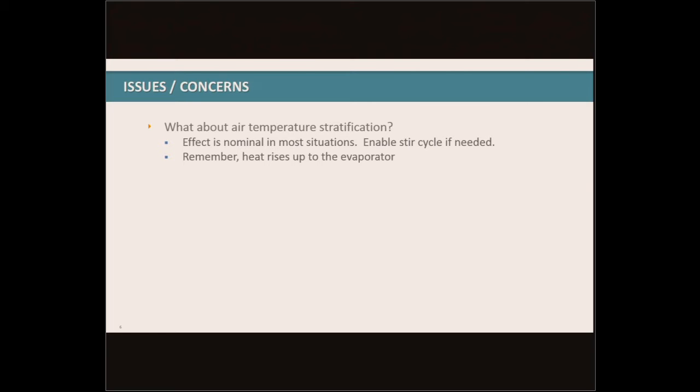The important thing to remember is that heat actually rises. We all know that heat rises. So if we turn off the fans, we are going to get some air stratification. The heat's going to rise up to where the temperature sensor is located by the evaporator. It's going to trigger the evaporator to go ahead and kick on again, and it'll start the refrigeration cycle. So it's a natural way to keep the refrigeration cycle going with keeping the fans off when they're not needed. The other thing to remember is that air temperature does not always equal product temperature. If we're trying to maintain a zero-degree product temperature in a freezer, if we have a little warm spot that's plus two, plus three degrees temporarily, the product temperature's not going to change. It's still going to be maintained at the zero degrees.